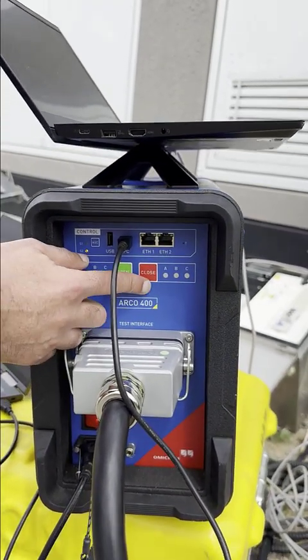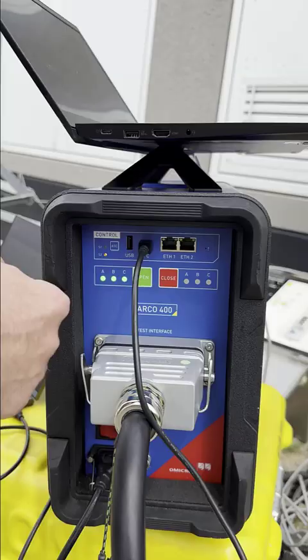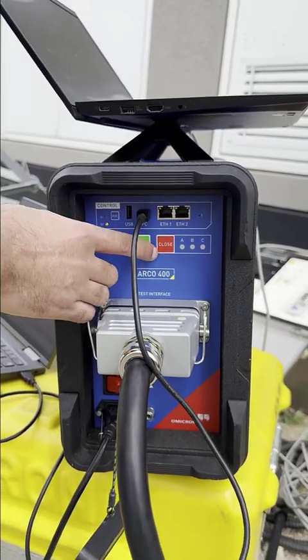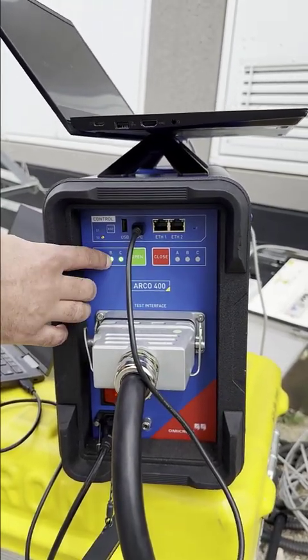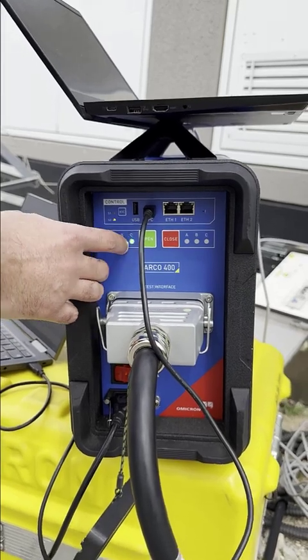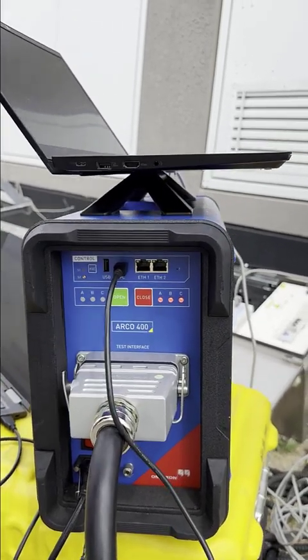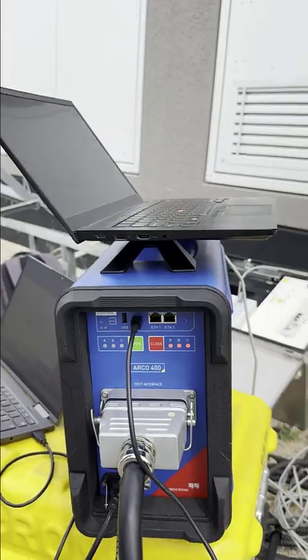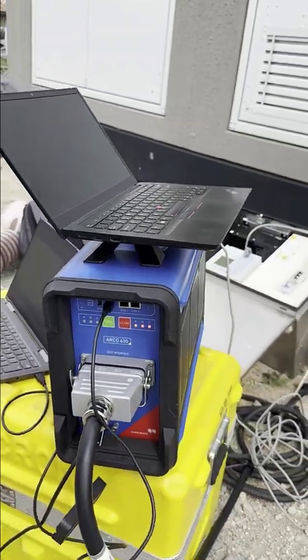You can use it from the front port to give close and open command for the circuit breaker. And you can see also the indication, as you can see, in green if the breaker is open and in red if the breaker is closed. Also you can make sure about the local HMI of the protection relay. So here is the connection.